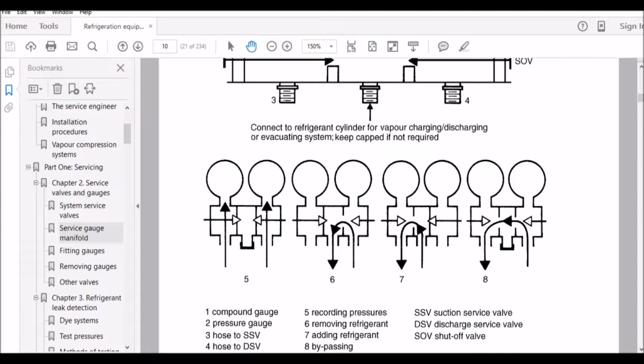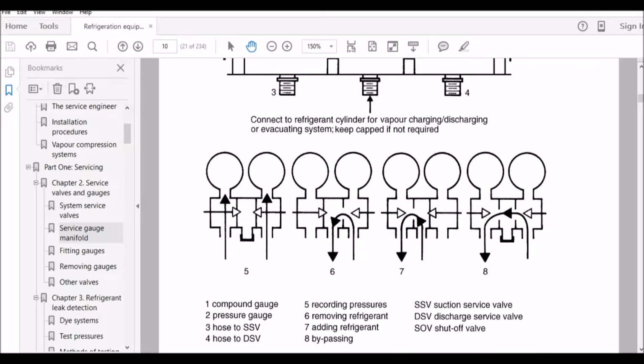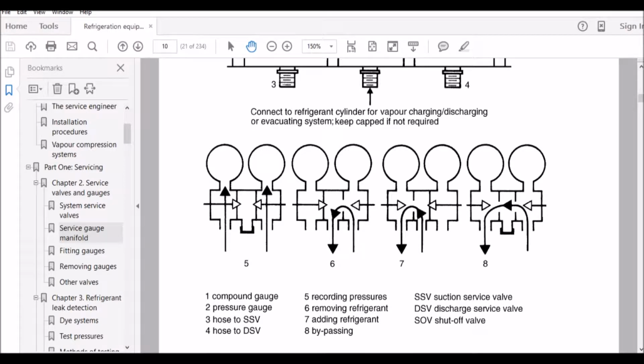And then this last one is showing that if I have the high and the low open, refrigerant will go between the two. So it will pass from the red side to the blue side. Obviously the arrows are going to the left because we're going to have higher pressure. So effectively the high side will dominate. In other words, the high side will go across into the low side and equalize across. But you will constantly be getting pressure coming from the high side across into the low side if we have both manifold valves open.